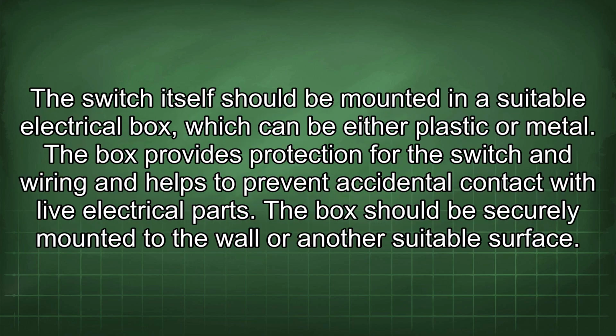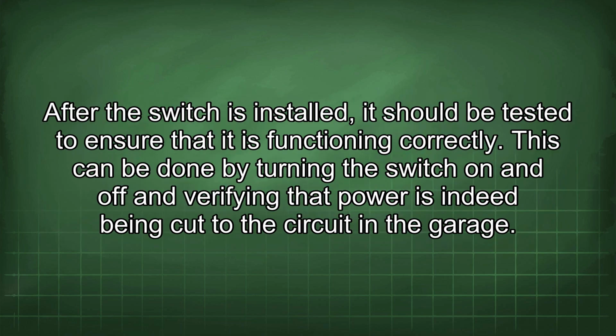The switch itself should be mounted in a suitable electrical box, which can be either plastic or metal. The box provides protection for the switch and wiring and helps to prevent accidental contact with live electrical parts. The box should be securely mounted to the wall or another suitable surface. After the switch is installed, it should be tested to ensure that it is functioning correctly. This can be done by turning the switch on and off and verifying that power is indeed being cut to the circuit in the garage.